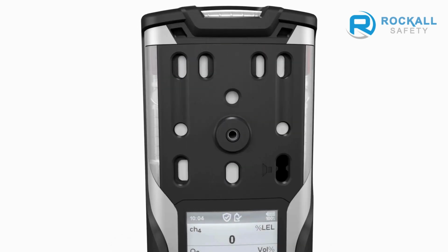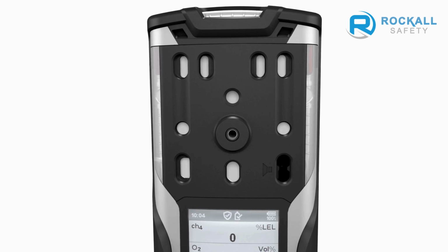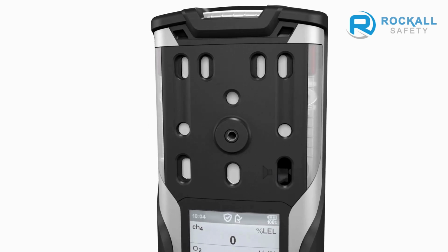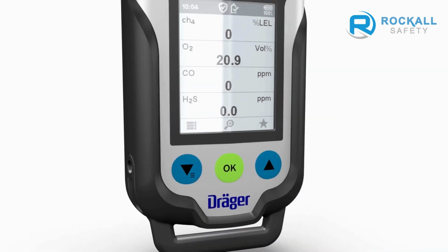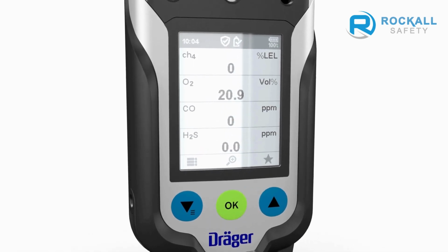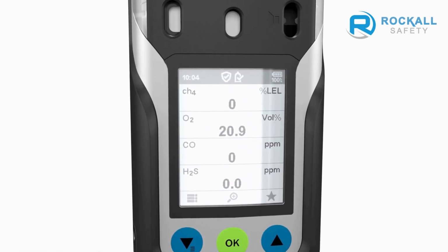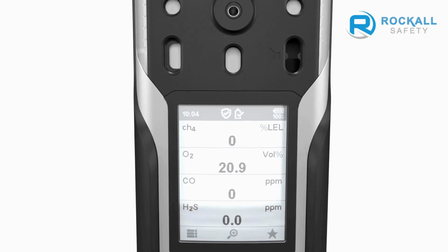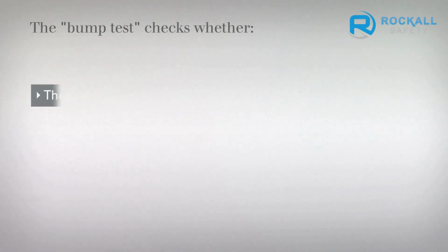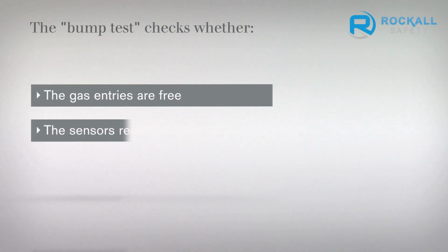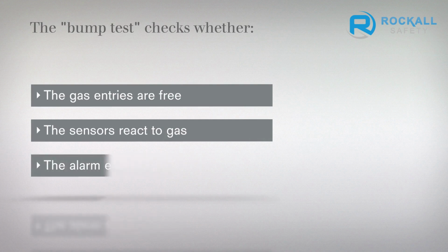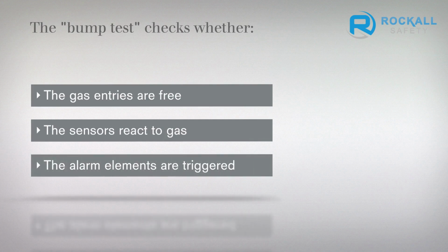If national regulations exist, the bump test must be performed in accordance with these regulations. A malfunction may lead to incorrect measurement results, which in turn can cause serious damage to health. The bump test checks whether the gas entries are free, the sensors react to gas, and the alarm elements are triggered. If the device fails the test, perform a calibration.